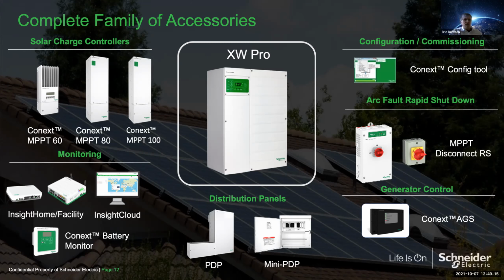Config tool allows the exceptional installer to calibrate AC voltages for multi-unit systems, and also save configuration files for quick and easy configuration of cookie cutter systems. And then we also have our disconnect RS for our charge controllers to provide arc fault and rapid shutdown requirements for rooftop solar according to NEC 690.11 and 690.12. And then last but not least, we have our automatic generator start module for starting and stopping a generator according to triggers such as low battery voltage or low battery state of charge. Next slide.